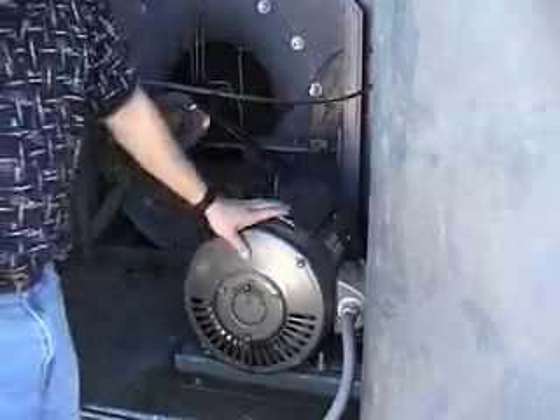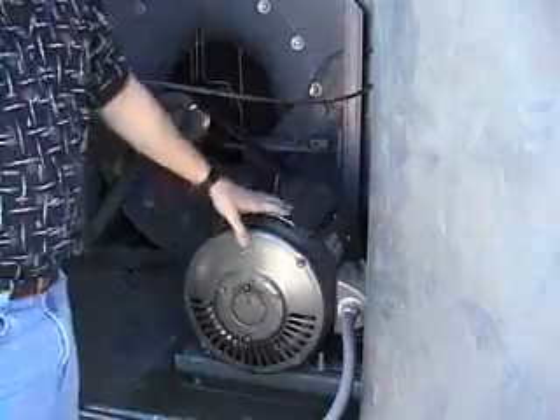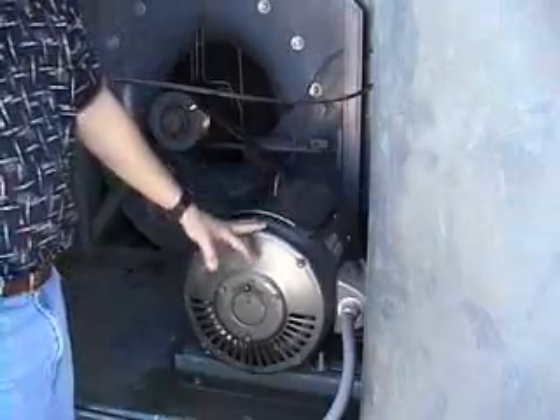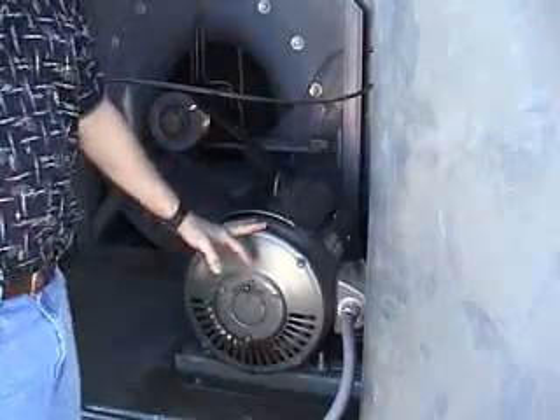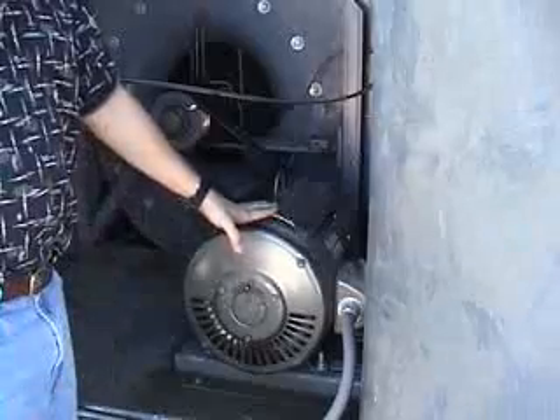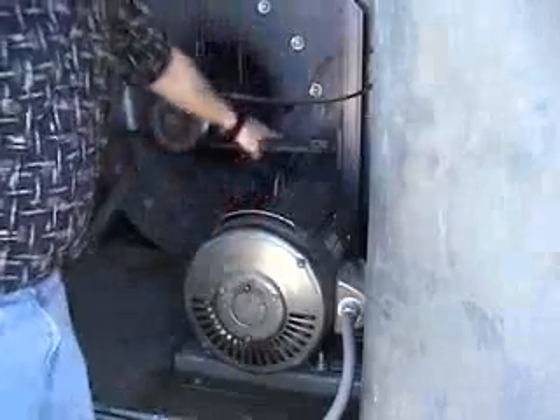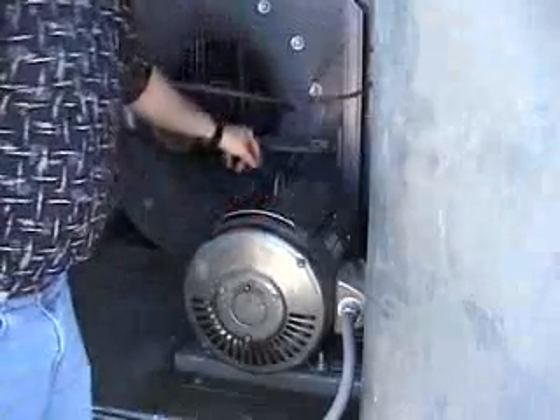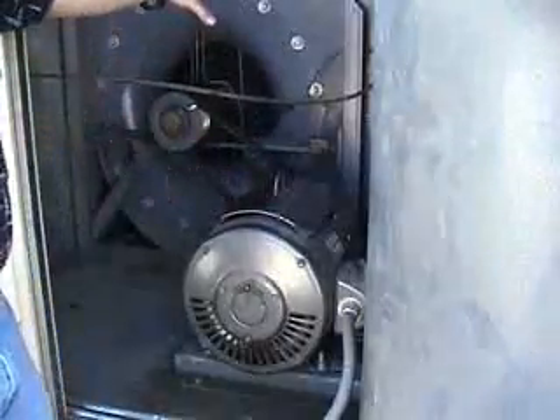This is the AC motor right here. It's an induction motor. This is a 25 horsepower motor. It runs on 460 volts, and it runs at about 32 amps. If we go above that, we'll burn it up. This is connected by a belt and pulleys, sheaves, to the supply fan.